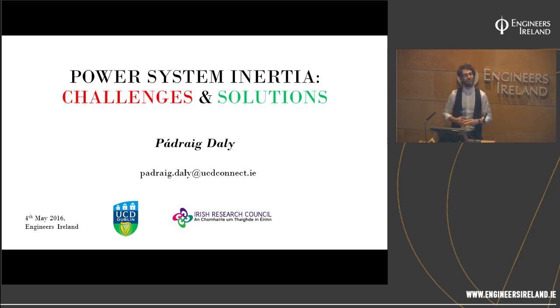And the first one, about the asynchronous limit, it's going to change with every power system. In some systems you will go as far as you hit your stability limit, and that could be frequency, voltage, or transient stability. For different systems it's going to change. So I don't think it's fair to compare systems, because the mode of stability that's hit first will change. Now you can fix that and push out the envelope even further, and then you'll hit another form of instability, and you'll grapple with that.